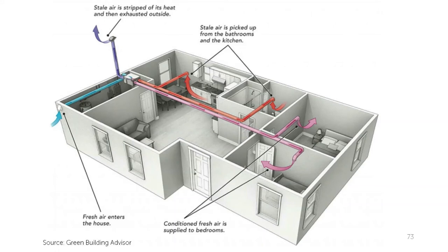How does the fresh air need to be filtered and conditioned prior to distribution inside the home? What about distribution ducting for ensuring that you get the air to the room you want it to go to, and the all too often forgotten placement and diffusion of supply air in the room, and how will the system be maintained? Working through these design criteria helps to identify the appropriate size and type of system needed for the project. As with any good design, the process is iterative and a balance between science and art, but certainly more science than art.